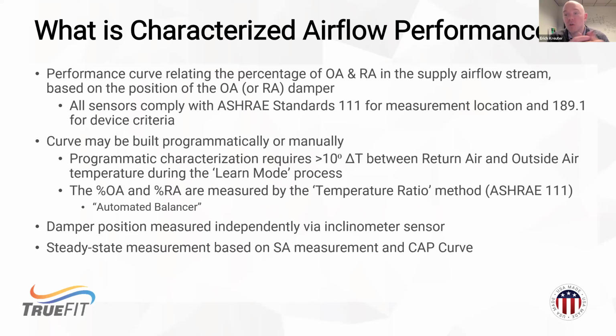It goes through a learn mode sequence. This takes about 2 hours to characterize all 3 of these airflows and the temperature and pressures, after which we're producing the measurement with the curve, the inclinometer, and that supply airflow total.